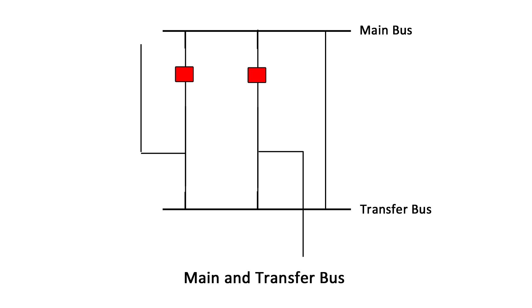Then the circuit breaker to be maintained is opened and isolated on both sides. Circuit protection will be disabled in this maintenance arrangement. When a tie circuit breaker is present, circuit breaker maintenance is achieved by closing the tie breaker.